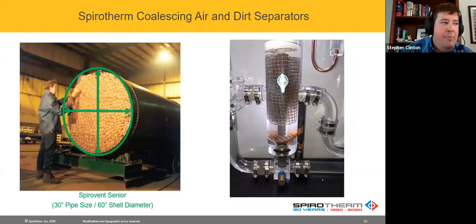I thought this was a good slide, something you might like to see. This is a unit that's a 30-inch pipe connection, 60-inch shell diameter. That handles a lot of flow, but what you'll see is all of these elements here are the spiral tube element that you saw earlier, which is basically a whole lot of these. So when the water comes in one side and goes out the other, it has to go through this, air and dirt both. If you can zoom in, you'll notice on the bottom of the float there are air bubbles here. You can also possibly see small air bubbles here as well. They're coalescing. That's where the heavy lifting is done.